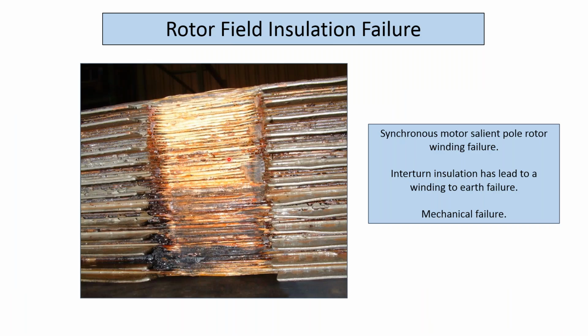And this is a failed field winding. This started off as an inter-turn failure, so the turn-to-turn insulation failed, but probably because of stress of the V block pressing against the insulation, and it eventually failed with a failure to earth. Otherwise, it would have been very difficult to pick up.